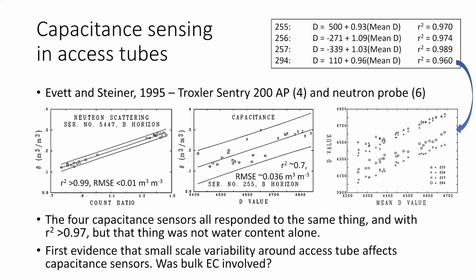error. And then for the capacitance sensing, we see a much larger root mean squared error, much larger 95% confidence intervals. And we see some values of the D value, which is a sort of a frequency scaled frequency value, that were larger for the dry soil than they were for the wet soil. Now, this was very confusing, but NRCS had reported to us that sometimes their sensors would tell them the soil was wet when it was dry, which is why we did the study.